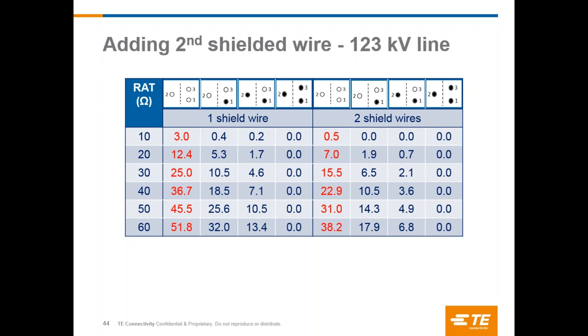In this case, as you have a shield wire, the bottom phase is the most exposed phase because it's less coupled, being at more distance from the shield wire. For this reason, higher transient voltages are established on this specific phase, with higher probability of back flashover occurrence. So you start protecting the shielded line, in the case of vertical or triangular lines, on the bottom phase. In the third column, you're installing arresters on the bottom and the middle phase, and in the fourth column on all phases. Similar configuration for two shield wires.